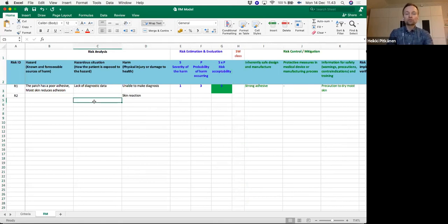But now, since we're in the principles, I won't expand this any further, but just to let you understand that it is also a balance of populating such a table. You must be aware of not overpopulating it and only putting the meaningful risks in it. Especially if it's, for example, an electromedical device, from the 60601 standard series alone you might have tens, or hundreds, of lines of risks to consider. So that is quite a load of information to put in a table.